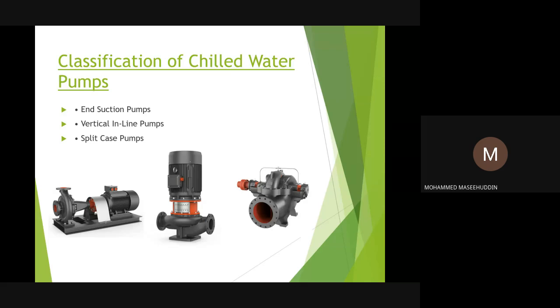So wherever there is a restriction of space, these pumps are used mostly in the primary circuit, but we can also use them in the secondary circuit as long as the building size, the tower size, is not very high. Maybe up to 45 or 55 kilowatt motors, we can use these pumps, whether in the primary circuit or the secondary circuit.